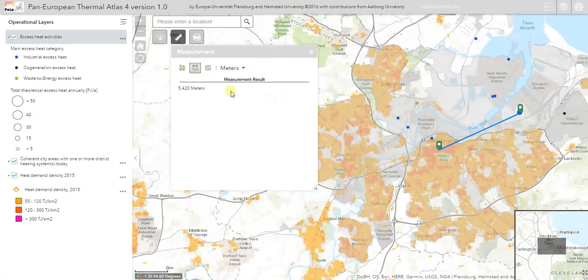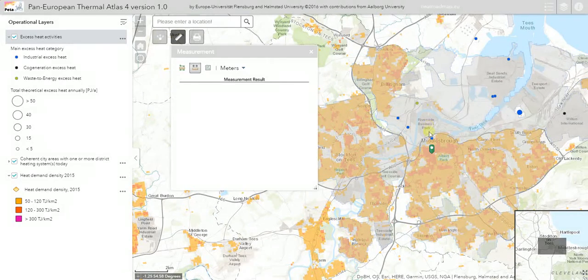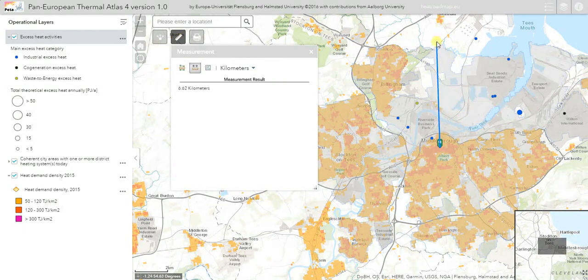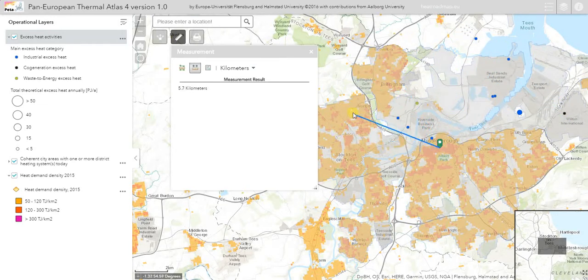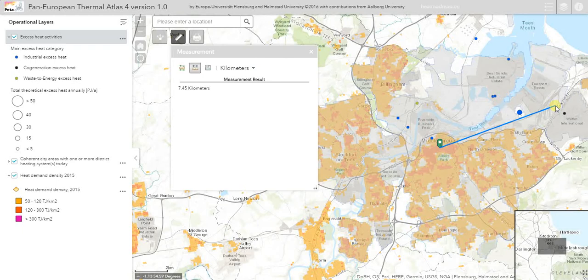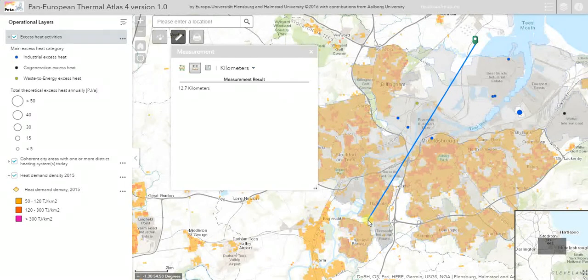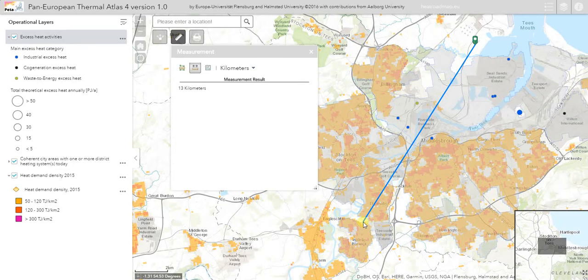Looking at the entire city for a medium-term perspective, measuring from the city center of Middlesbrough out to a radius of approximately 8 to 10 kilometers, we can get access to about three times more excess heat than we need to heat the city in total. Going the other direction, from the furthest facility to the furthest edge of the city is about 12 kilometers — which is very short in the context of district heating transmission pipes.